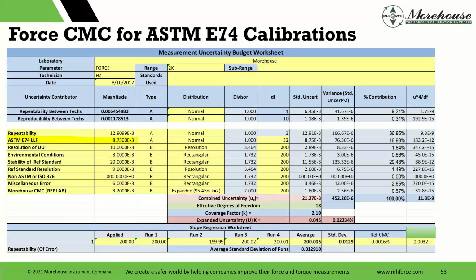So again, what does a budget look like? We're going to do this in a calibrating machine. At the end of the day, if we do E74, we could do an ISO 376, but this example is E74. That lower limit factor, we're going to have all of these, add them up, Morehouse reference CMC. This is an actual budget, and this was for the PCM machine. And look at our expanded uncertainty down there.